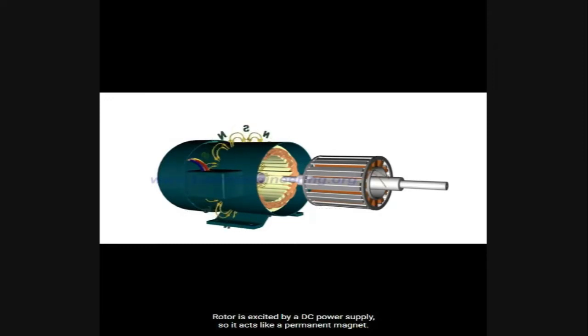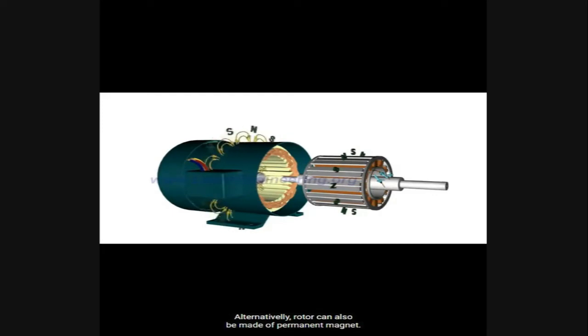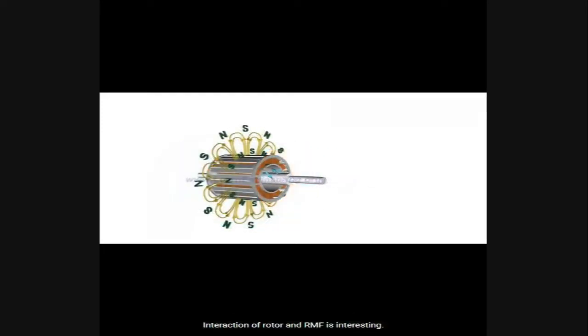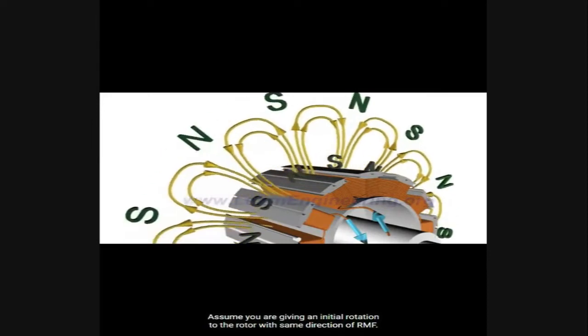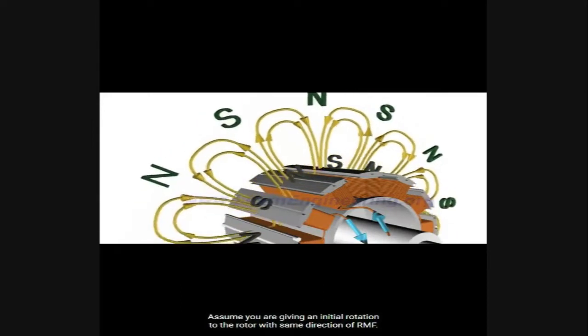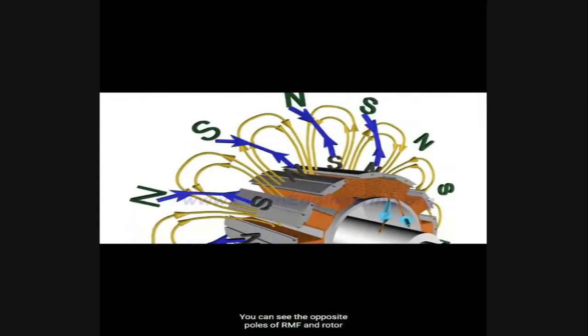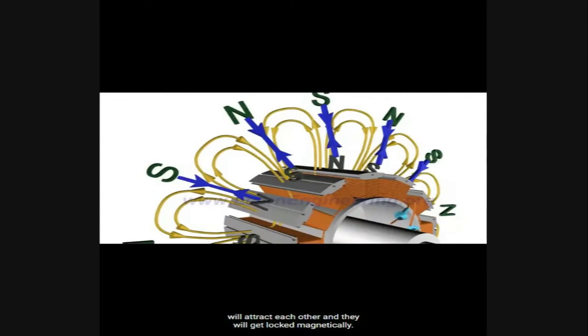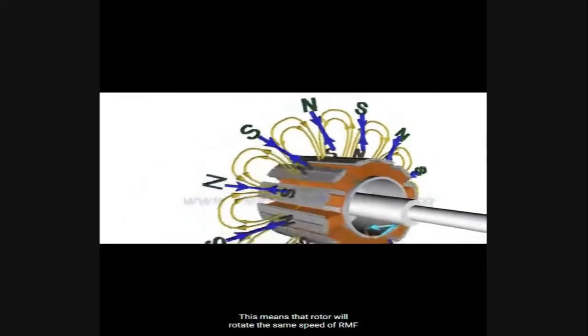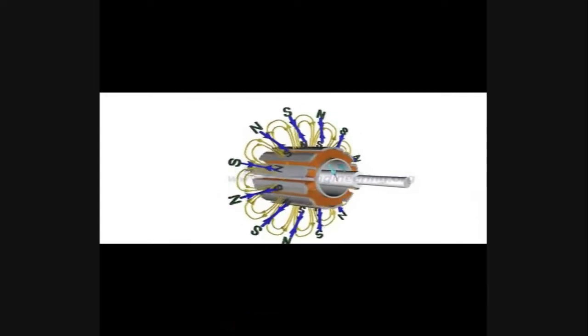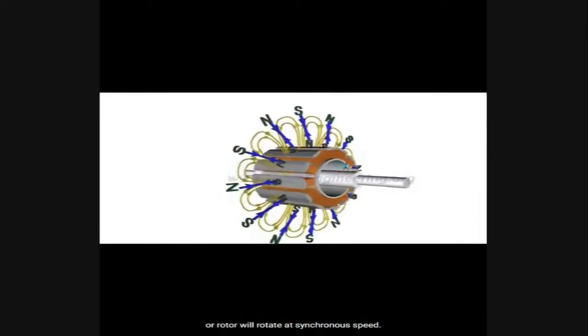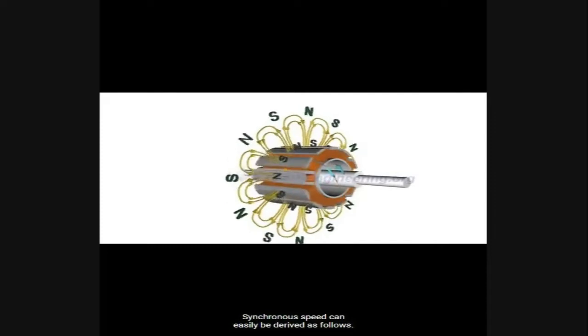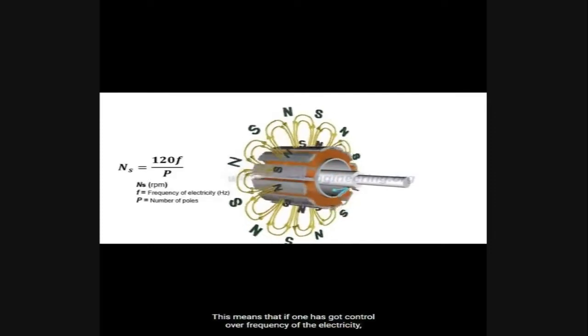The rotor is excited by a DC power supply so it acts like a permanent magnet; alternatively, the rotor can also be made of permanent magnets. If the rotor is given an initial rotation in the same direction as the RMF, the opposite poles attract each other and get locked magnetically, causing the rotor to rotate at synchronous speed.